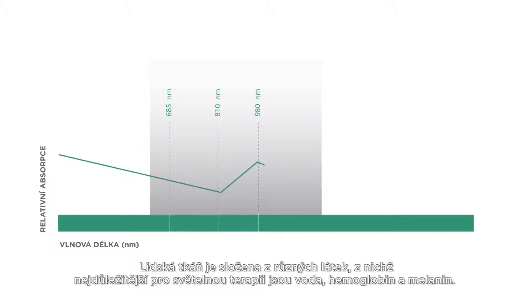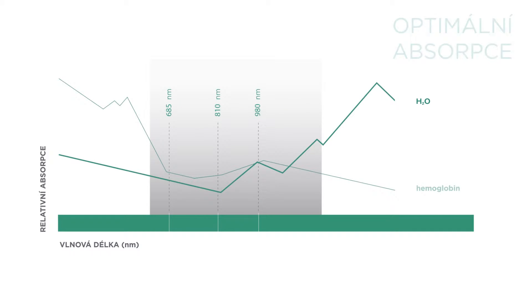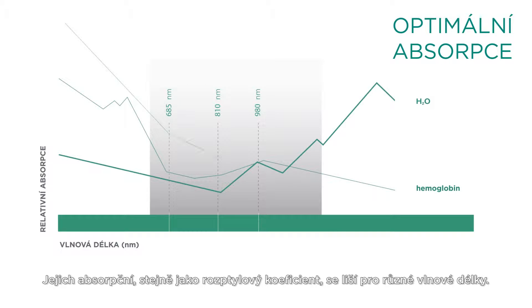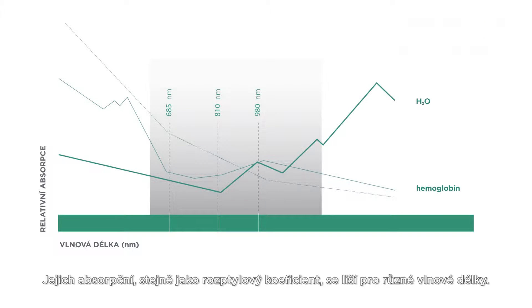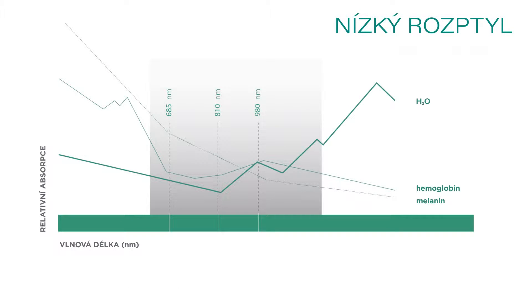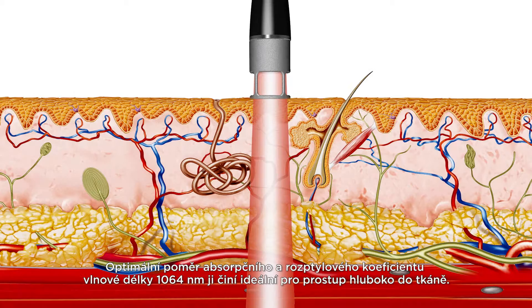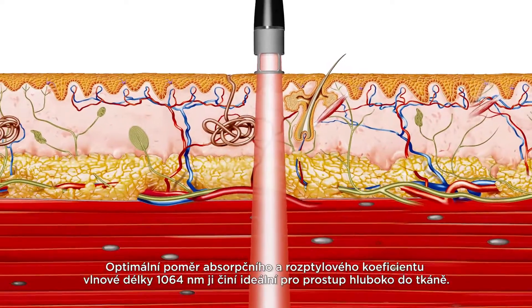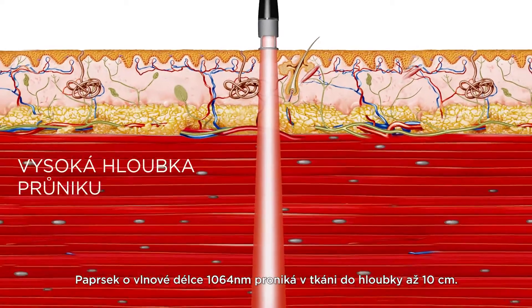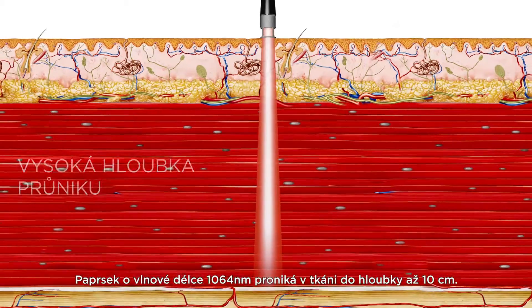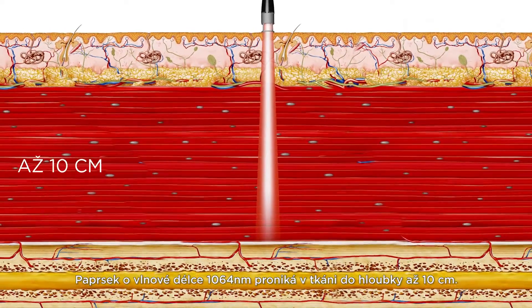Human tissue is composed of various components, of which the most important for laser irradiation are water, hemoglobin and melanin. Their absorption, as well as the scatter coefficient, are different for different wavelengths. The optimum scatter-to-absorption ratio of the 1064 nanometer wavelength makes it ideal for deep tissue penetration, with a beam capable of reaching up to 10 centimeters deep into the tissue.